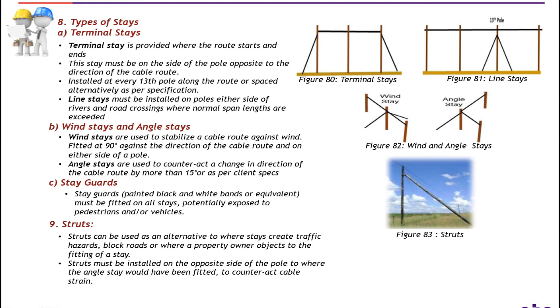Wind stays and angle stays. Wind stays are used to stabilize a cable route against wind, fitted at 90 degrees against the direction of the cable route and on either side of a pole. Angle stays are used to counteract a change in direction of the cable route by more than 15 degrees or as per client specifications. Number two: stay guards — painted black and white bands or equivalent must be fitted on all stays potentially exposed to pedestrians and/or vehicles.